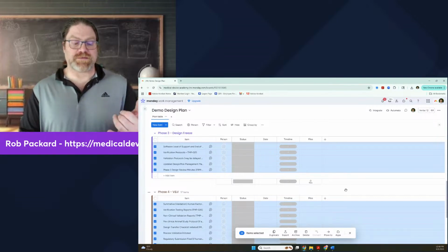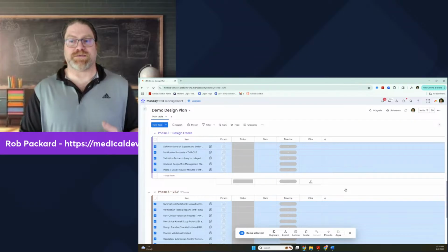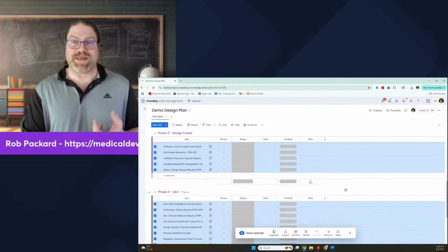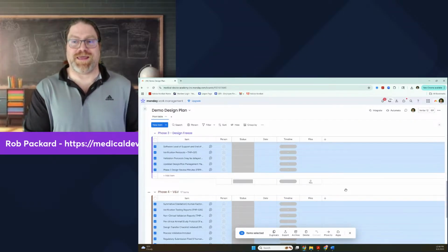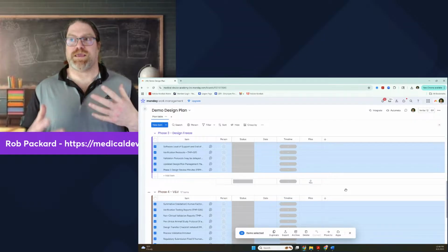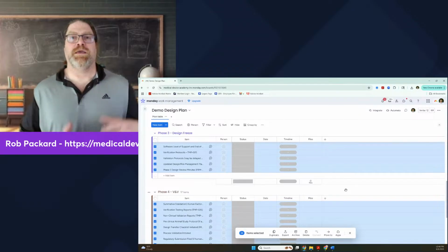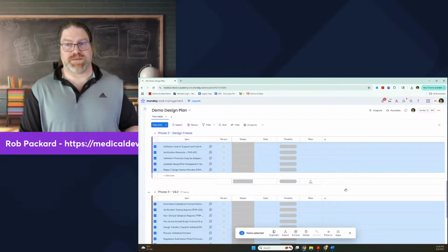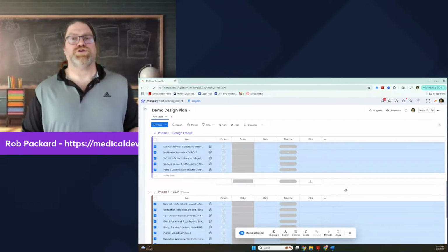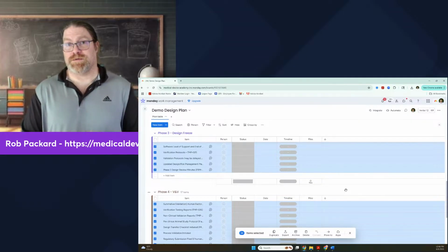The performance testing would be non-clinical benchtop, animal testing, clinical testing, could be cadaver testing. It could be finite element analysis. It could be a sawbones model. It could be the summative usability testing. All those are considered validation because you do them with a finished device. All the other testing you can do on parts of a device, potentially.